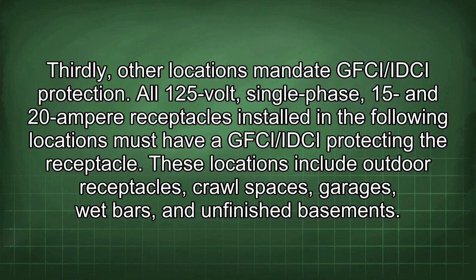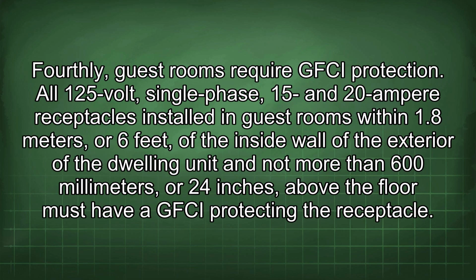Thirdly, other locations mandate GFCI/IDCI protection. All 125-volt, single-phase, 15 and 20 ampere receptacles installed in the following locations must have a GFCI/IDCI protecting the receptacle. These locations include outdoor receptacles, crawl spaces, garages, wet bars, and unfinished basements. Fourthly, guest rooms require GFCI protection. All 125-volt, single-phase, 15 and 20 ampere receptacles installed in guest rooms within 1.8 meters, or 6 feet, of the inside wall of the exterior of the dwelling unit and not more than 600 millimeters, or 24 inches, above the floor must have a GFCI protecting the receptacle.